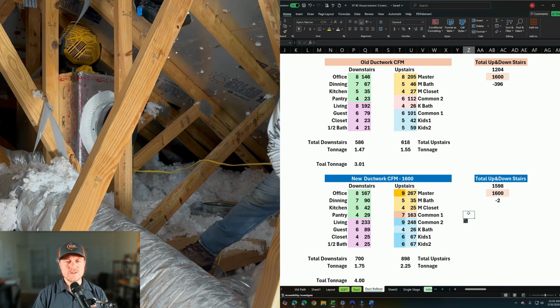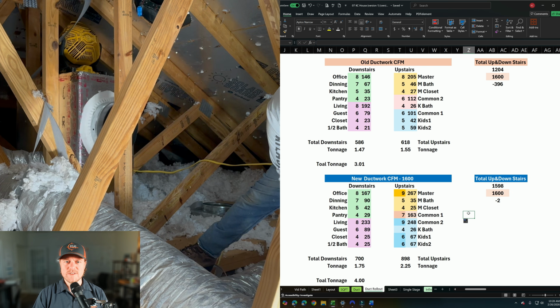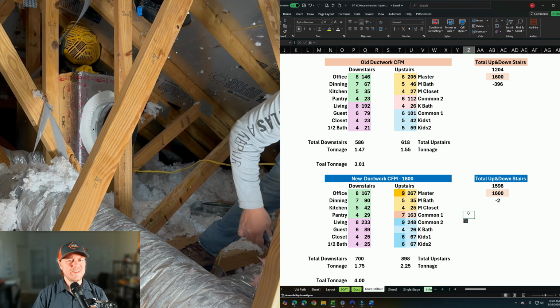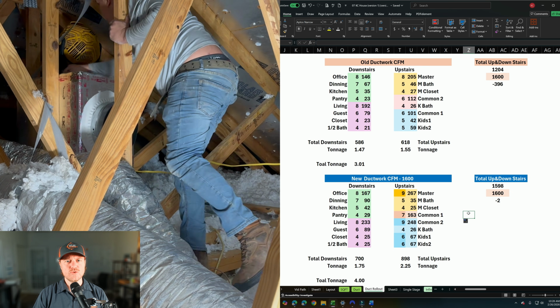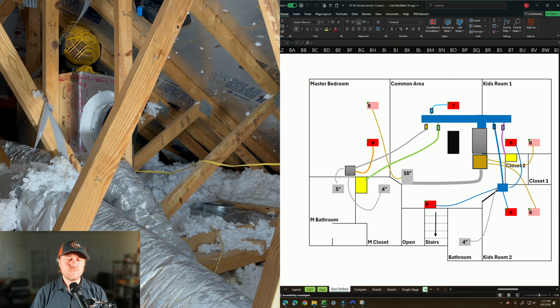A 6-inch duct should easily be able to supply 75 CFM. And what's happening here is the same thing that's happening in the master bedrooms. How I would solve this problem, which you could also apply to the master bathroom, I would pull the duct from the distro box and attach it directly to the supply trunk. That would then allow the duct to be 100% utilized.